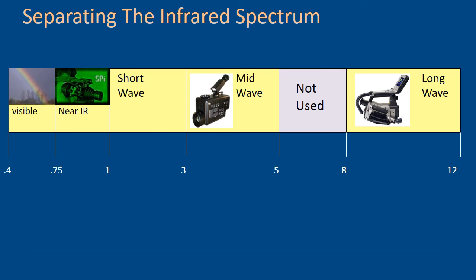Visible light is between 0.4 and 0.75 micrometers. Then we get into the near infrared which goes from 0.75 to 1. Short wave goes between 1 and 3 microns. The mid-wavelength is between 3 and 5 microns — not really used much today, though it was used extensively back in the day. Typical mid-wave cameras now would be things like gas detection cameras which are very specific for a certain job. Between 5 and 8 microns we don't use it — the atmospheric attenuation is such that it really isn't suitable for infrared transmission. The typical infrared camera — 99% of them — works in the long wave of 8 to 12 microns.